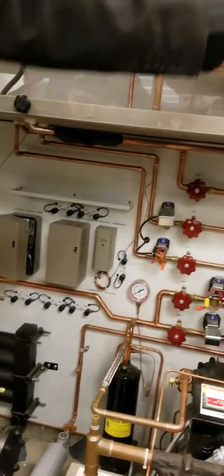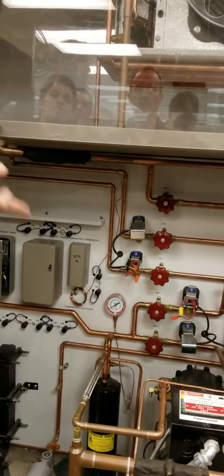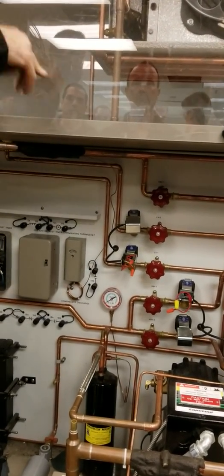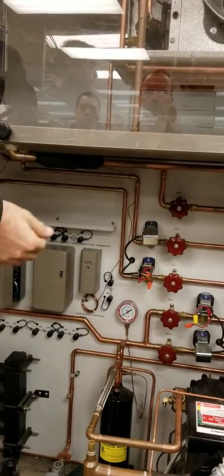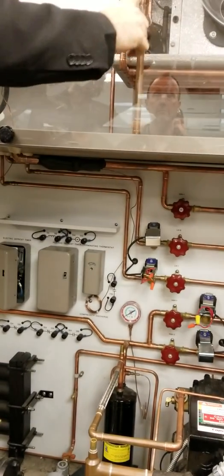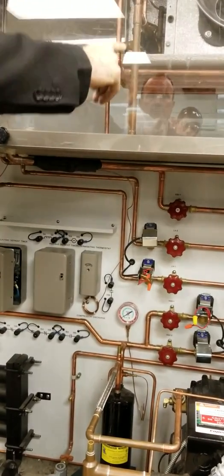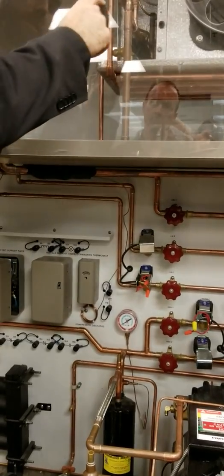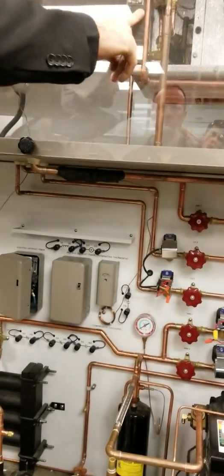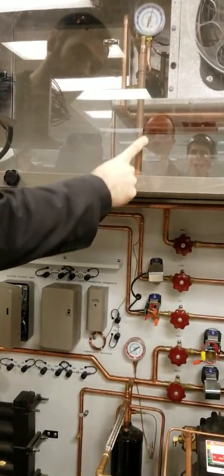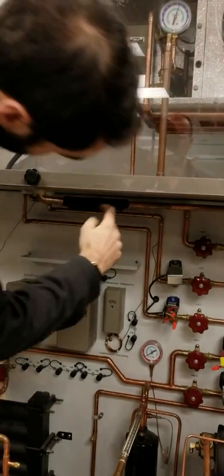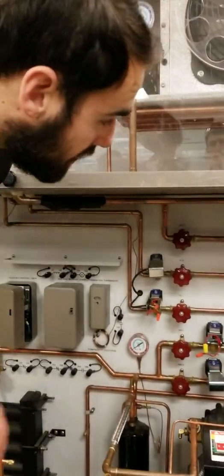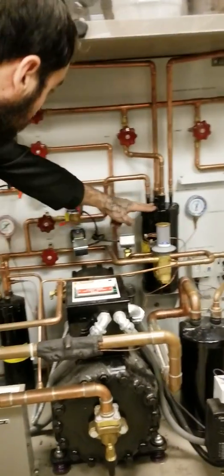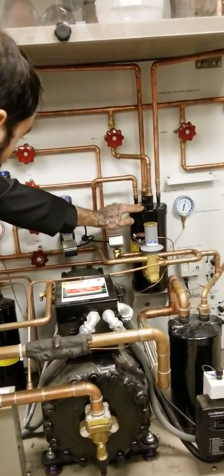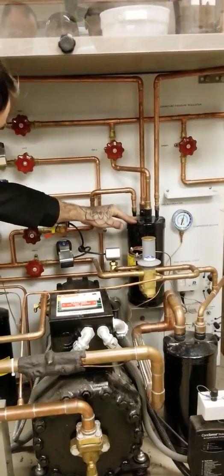Then you just have your typical evaporator operation. Air is going to be transferred over the coil. As that refrigerant has its pressure drop, it's going to absorb the heat out of the air, and the refrigerant will travel out through the suction line. You have your sensing bulb detecting your pressure to accommodate any pressure drop there and to feed the refrigerant properly.